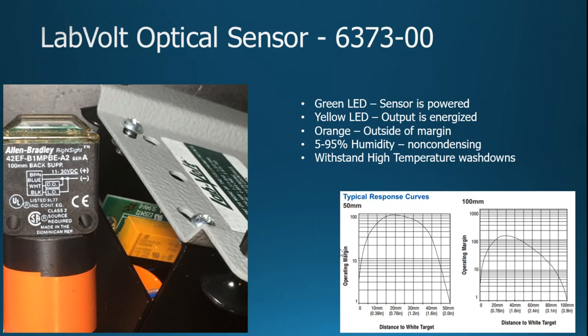So you can see this with the little graph down below on the bottom right. We have the 100 millimeter sensor here. And what this shows is that the white background target would be triggered at about four inches. However, it's right at the operating margin there. And what will happen is if you're just like a little bit outside 3.9, maybe at four inches, potentially the orange one would come on. And then when it was within the margin, the yellow would come on and would actually lock it. So this is hysteresis that occurs so that when you are actually moving out of it, the yellow might actually stay active. The orange is showing you that it's about to drop out or something is about to trigger the system. Or it shows you your object might be a little bit outside of the range.